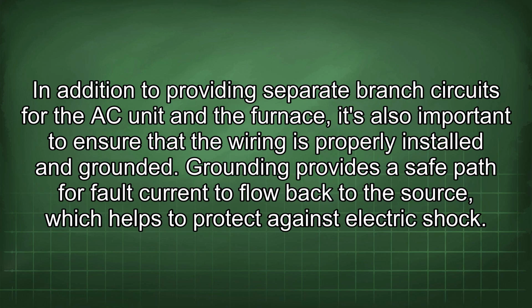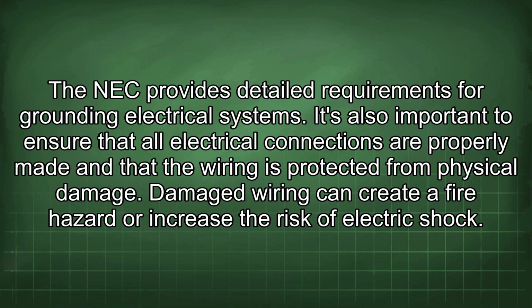In addition to providing separate branch circuits for the AC unit and the furnace, it's also important to ensure that the wiring is properly installed and grounded. Grounding provides a safe path for fault current to flow back to the source, which helps to protect against electric shock. The NEC provides detailed requirements for grounding electrical systems. It's also important to ensure that all electrical connections are properly made and that the wiring is protected from physical damage. Damaged wiring can create a fire hazard or increase the risk of electric shock.